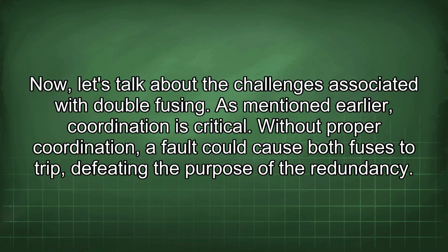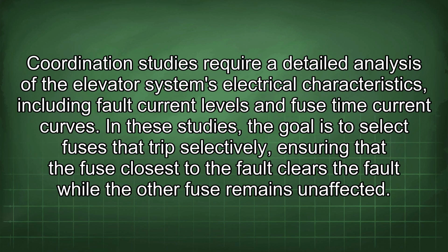Now, let's talk about the challenges associated with double fusing. As mentioned earlier, coordination is critical. Without proper coordination, a fault could cause both fuses to trip, defeating the purpose of the redundancy. Coordination studies require a detailed analysis of the elevator system's electrical characteristics, including fault current levels and fuse time current curves. In these studies, the goal is to select fuses that trip selectively, ensuring that the fuse closest to the fault clears the fault while the other fuse remains unaffected.